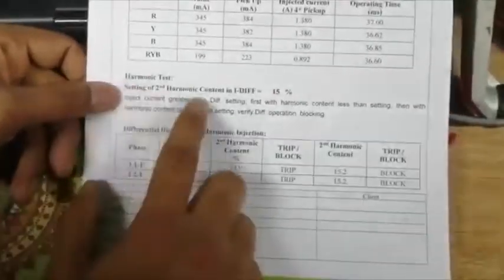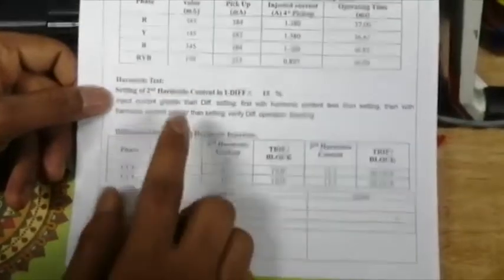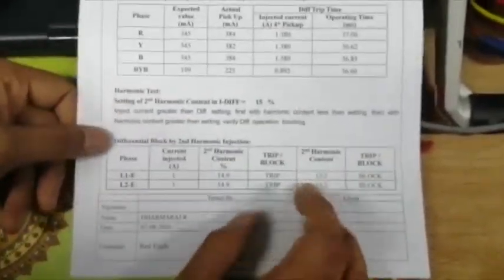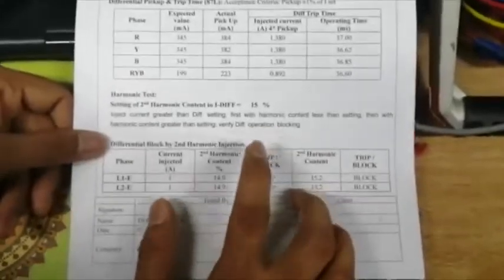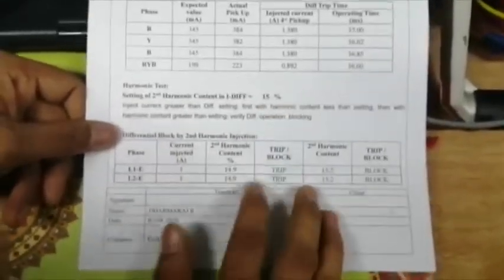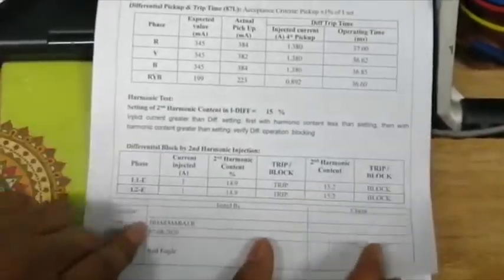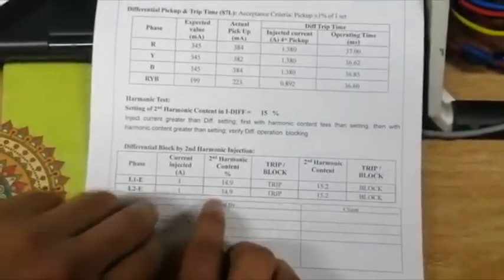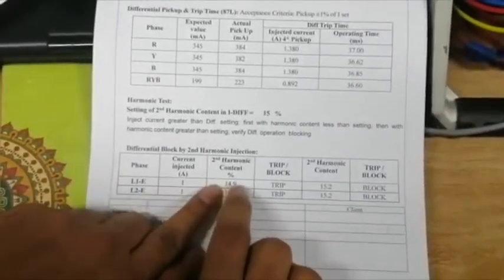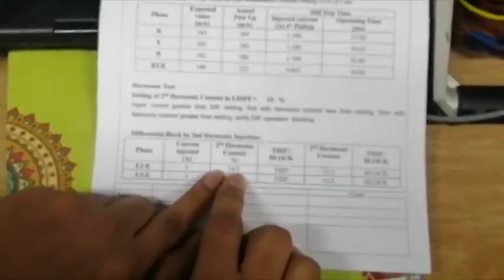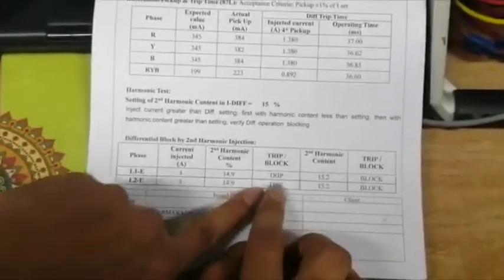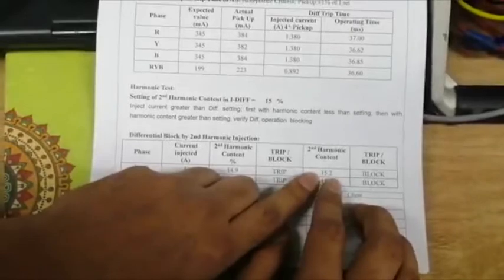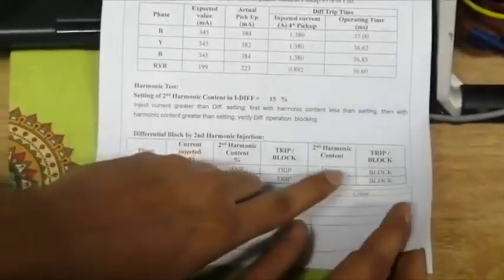Next test, harmonic test. If our relay detects harmonic content of more than 15%, then our relay will block the differential protection. If the harmonic content is less than 15%, then it will issue the trip. I just noted here for 14.9, it is less than our harmonic content, so it gave trip. More than 15.2, it is blocked.